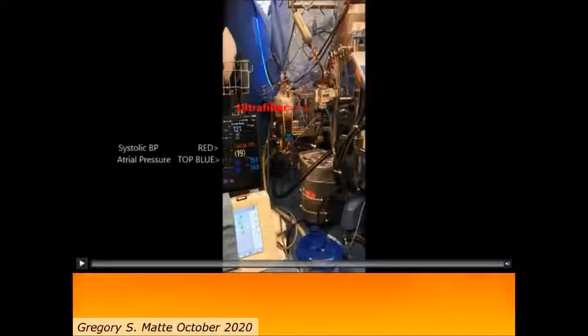This is the ultrafilter, and once again, during MUF, this is the venous line. The ultrafilter will pull from the venous line, pump it into the hemoconcentrator, and you'll notice this stopcock is turned so the blood flow will go into the oxygenator and not back to the reservoir. So let's look at the video.